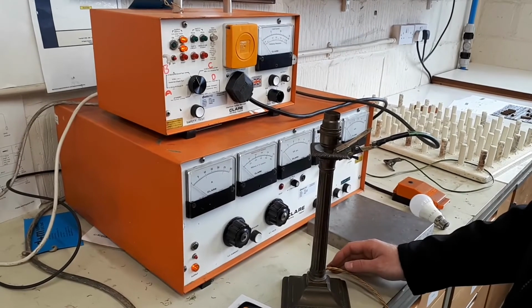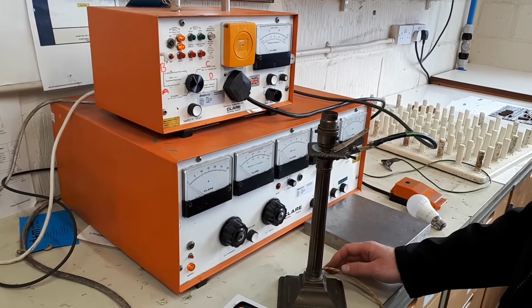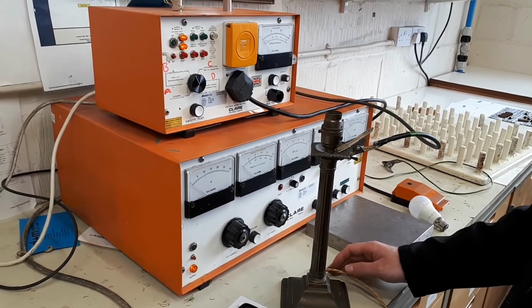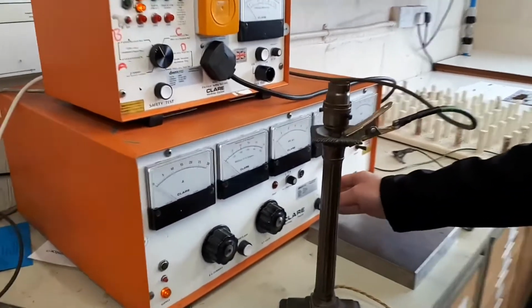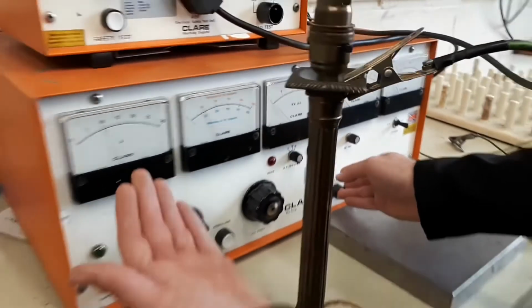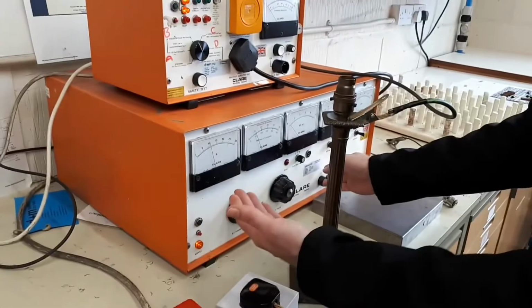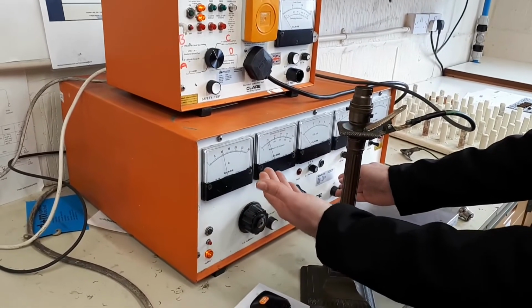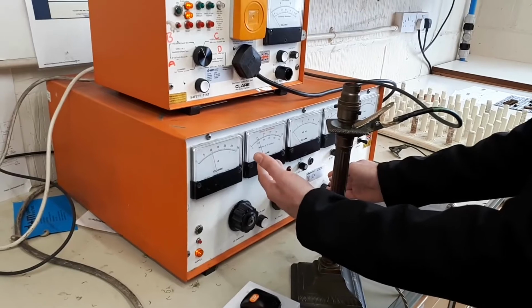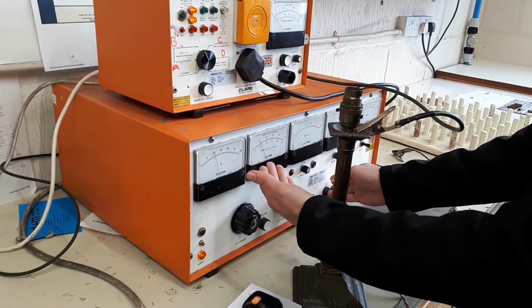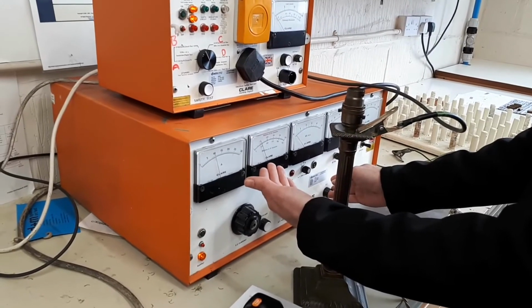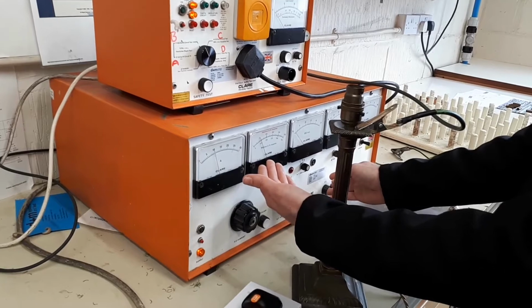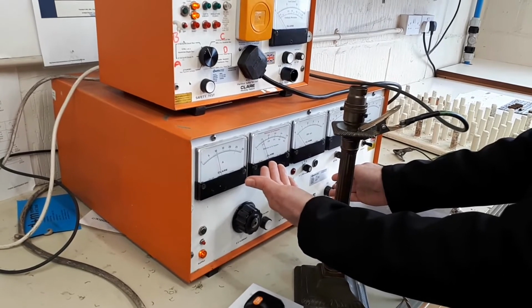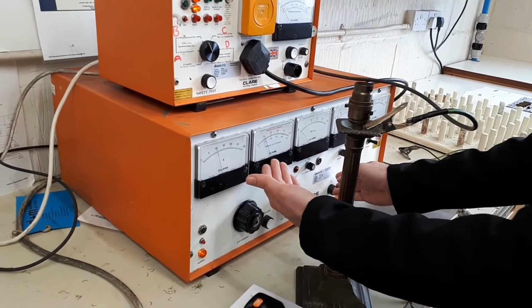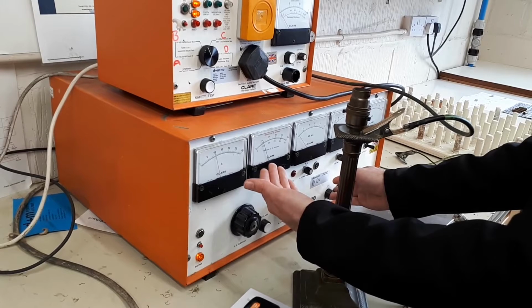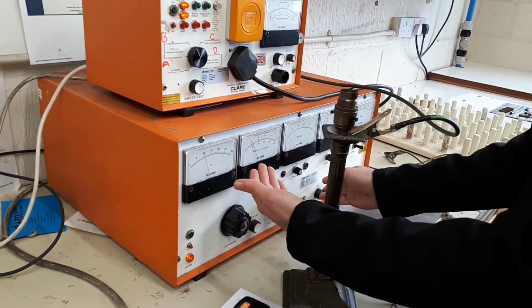The first test we carry out is the earth bond continuity test. We measure this with a test current of at least 10 amps. This ensures the fitting has a safe earth connection and only applies to class 1 fittings. This test checks the resistance of the earth connection. The result should not exceed 0.1 ohms, although a reading of up to 0.3 ohms is usually acceptable.